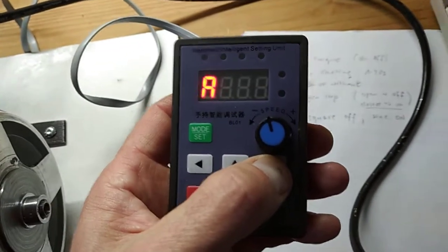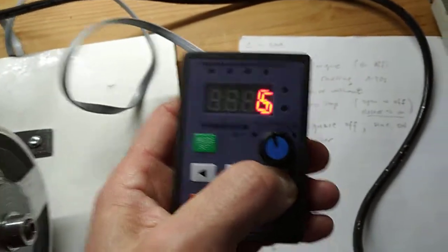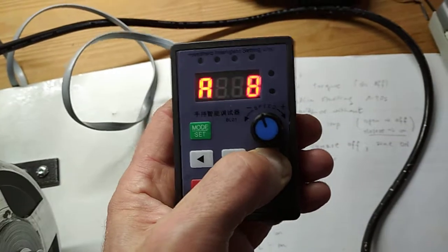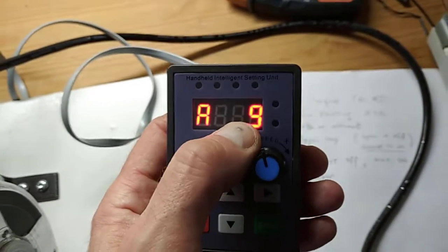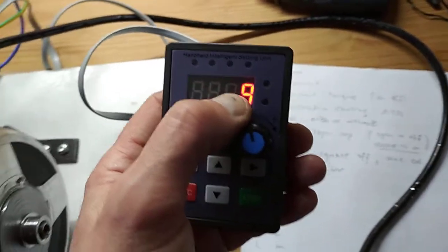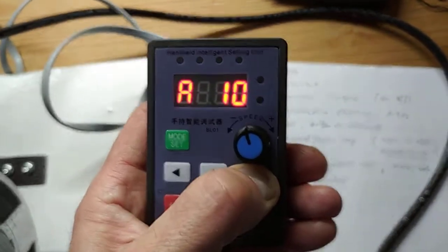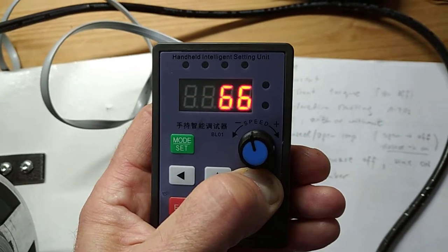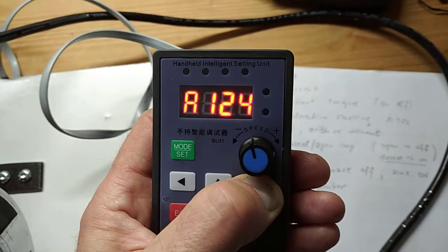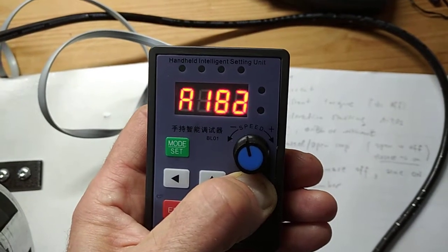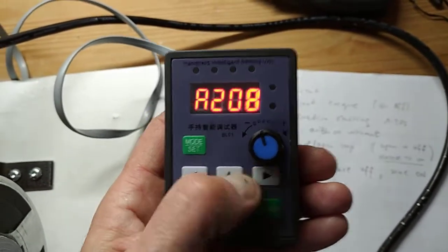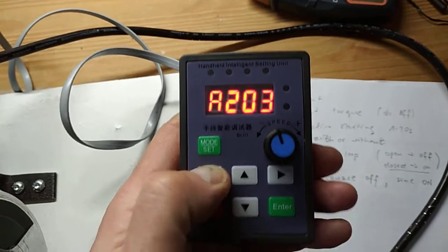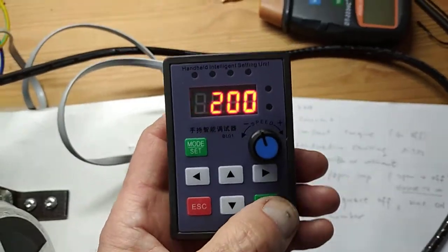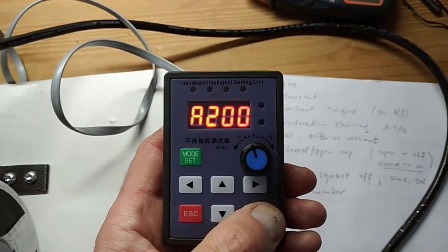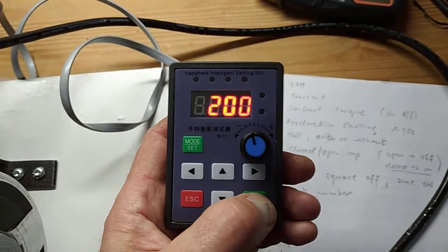Let's say we want to spin this motor at 2000 RPM. With the right arrow, we have to go to 200, because this is the count which you set here, multiplied by 10. So we're going to 200. The maximum RPM I will get here is now set for 2000 RPM.